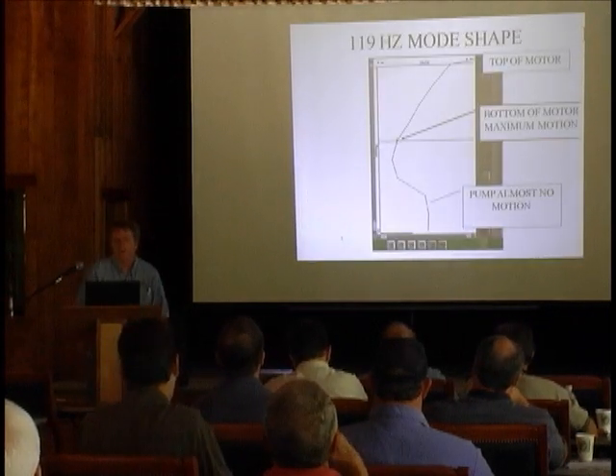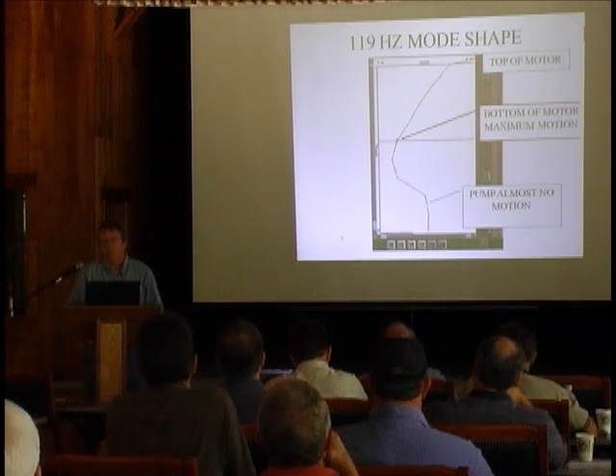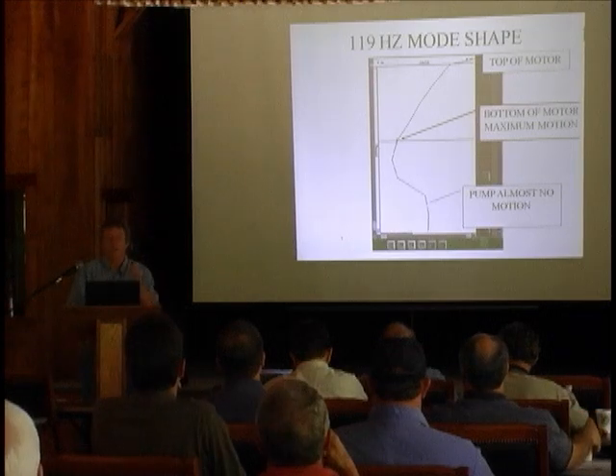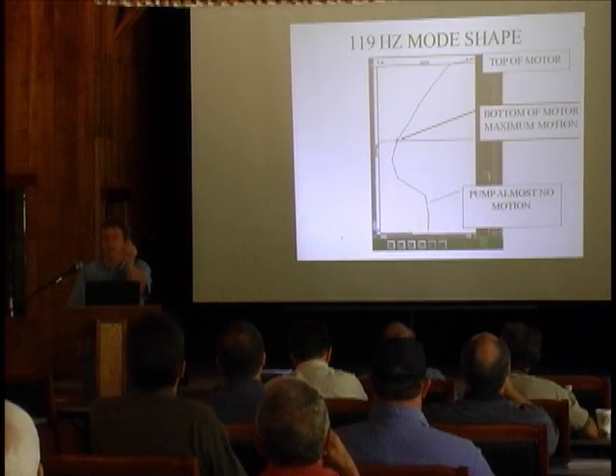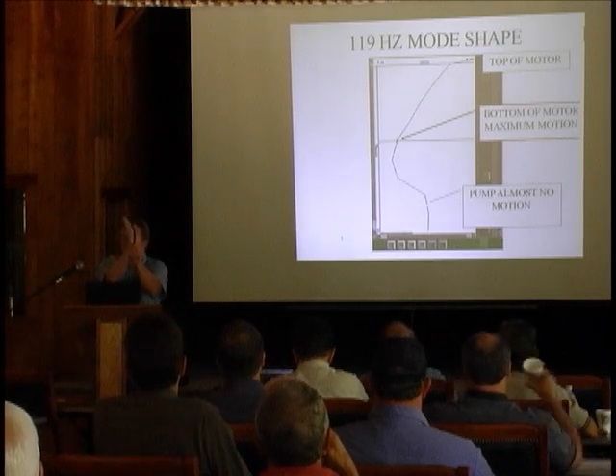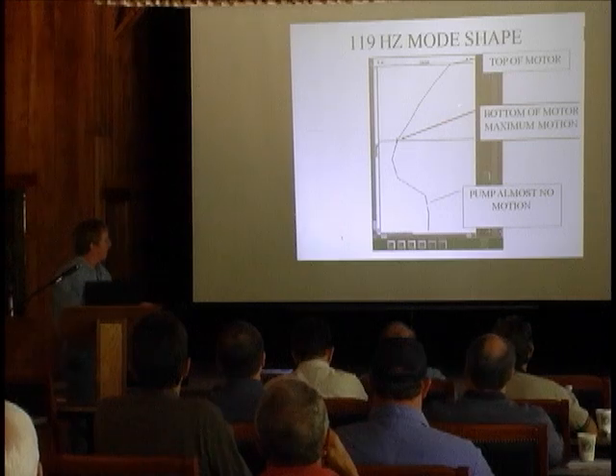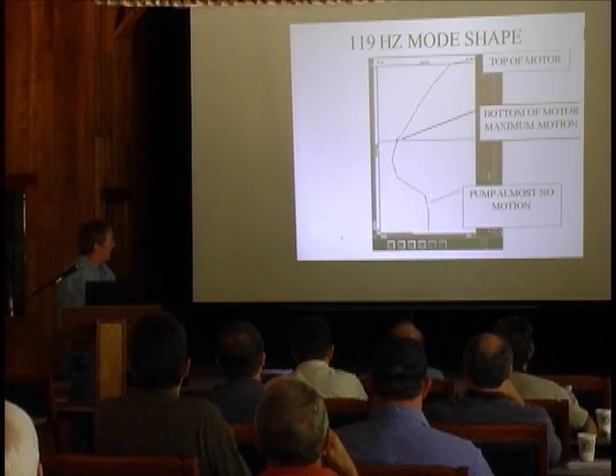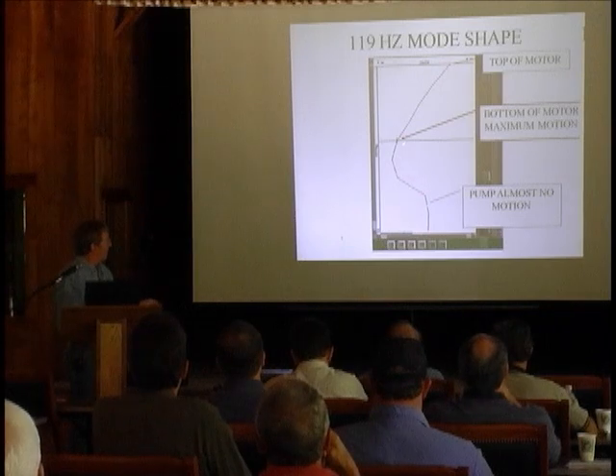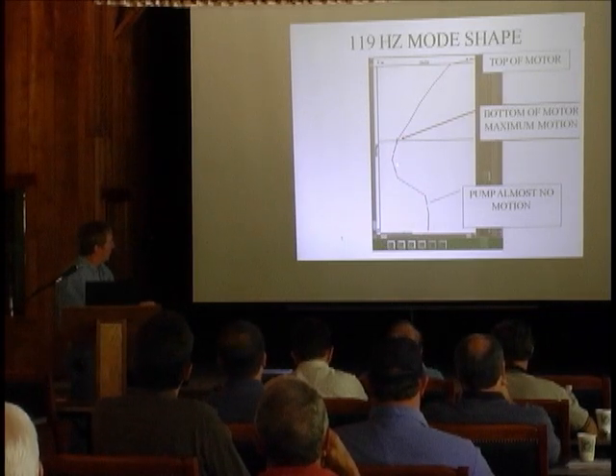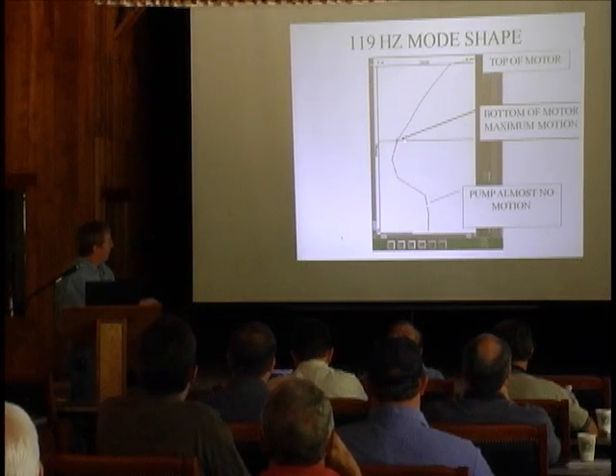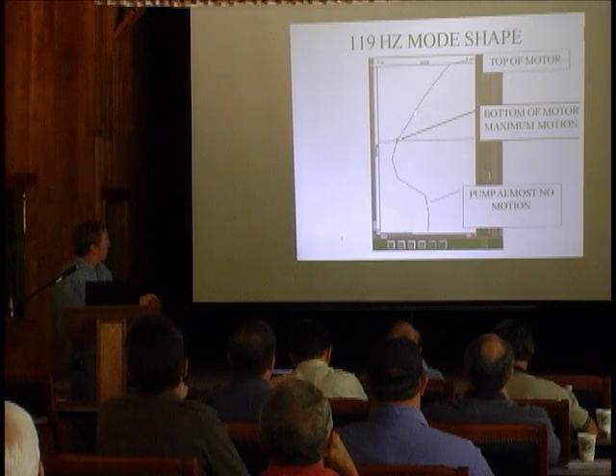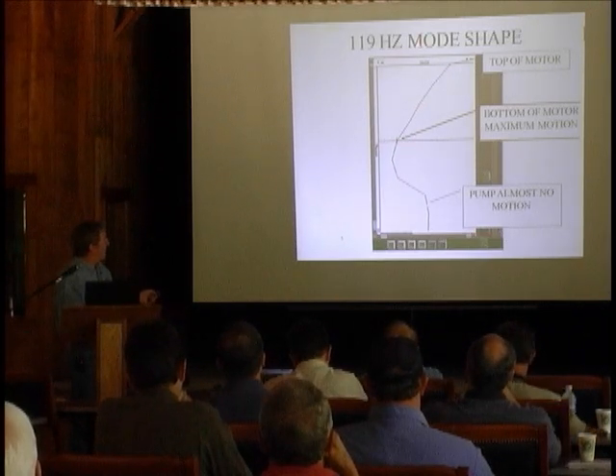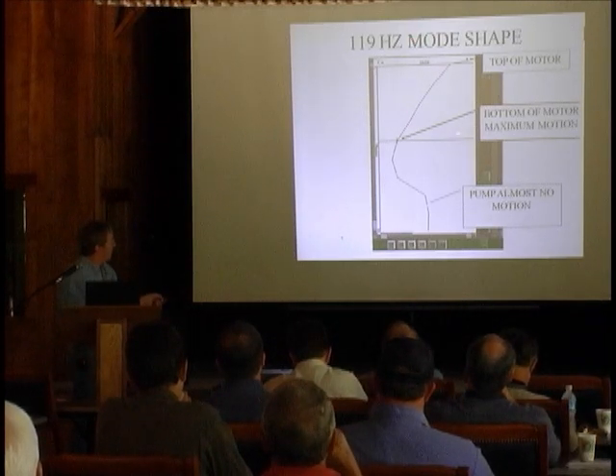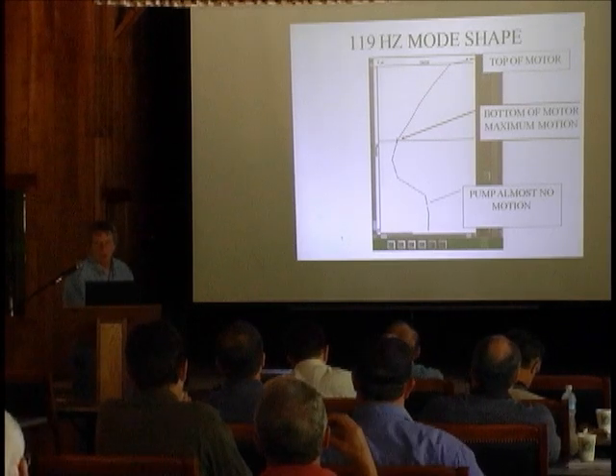Turned out, though, I know probably a lot of you have done vertical pumps, and vertical pumps generally are in 2 type modes, either the rocking mode if the base is weak, or the first bending mode. But this one was bending right in the center. This is 120 hertz. And on the pump, there was almost no motion. The bottom of the motor, and then this part distorting here was actually the pump casing. And so we're having a distortion in the top of the motor. And this was the mode shape, which was very, very close to 4 times the 30 hertz speed. So I have maximum at the bottom of the motor.